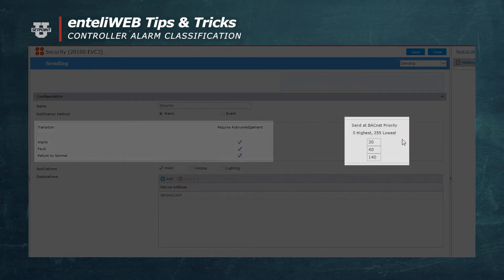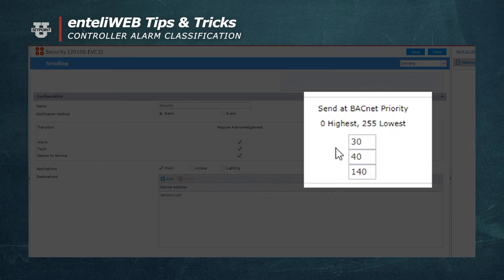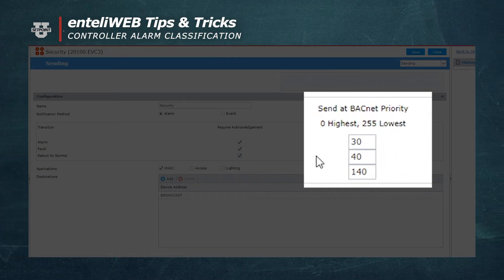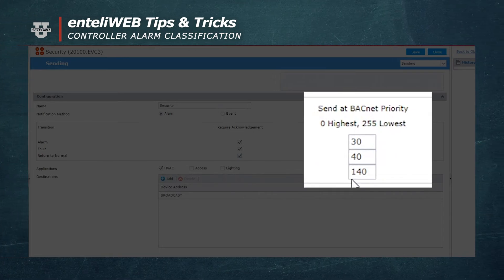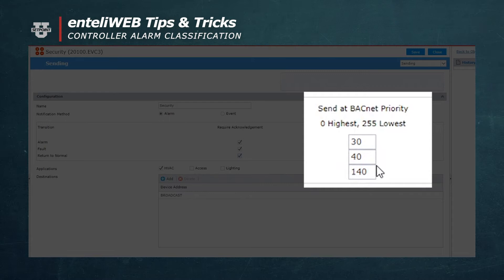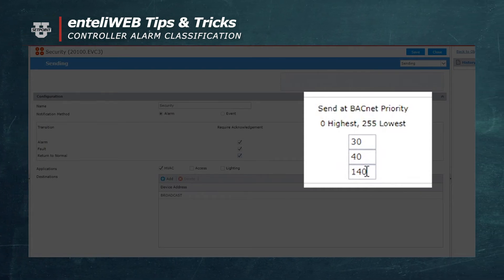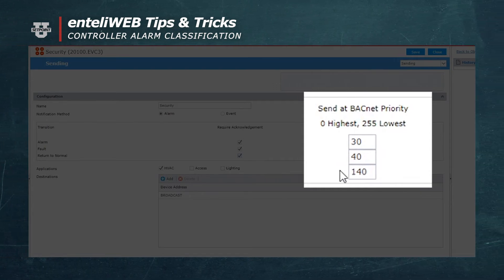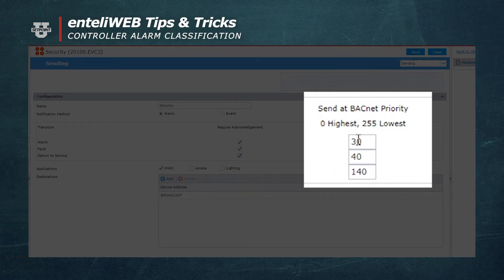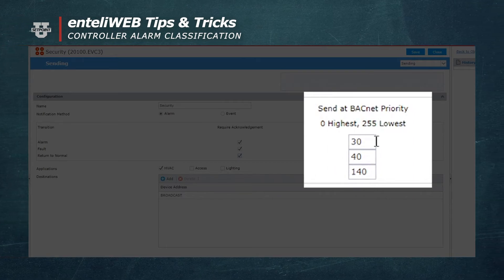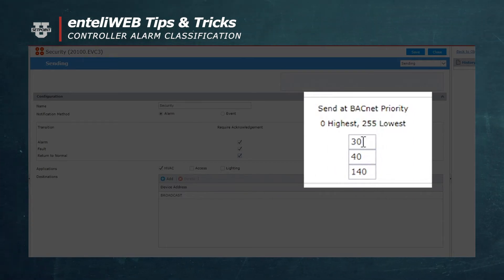There's also a list of priorities of the alarm, the fault, and the return to normal. You'll notice that the return to normal has a very high number. That means that's a low priority where a high priority is the alarm level itself which is 30.